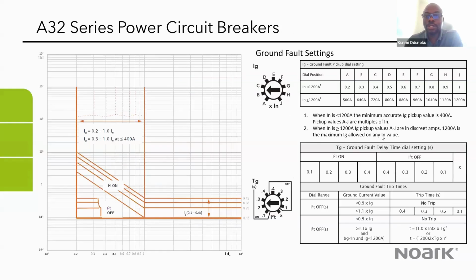And here are the settings that are available for the ground fault protection. We have pickup settings for less than 1,200 amps, and also above 1,200 amps. You can also introduce a time delay as well, as we've seen in this photo.